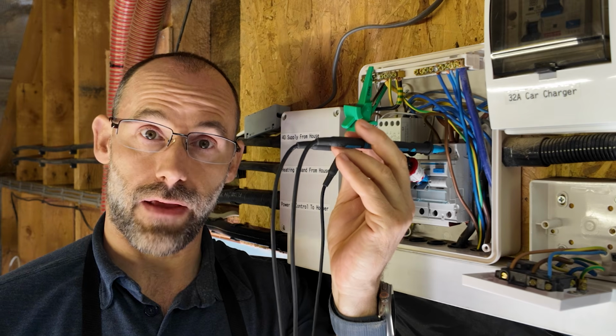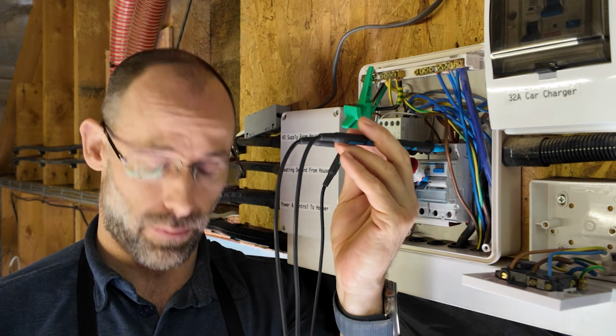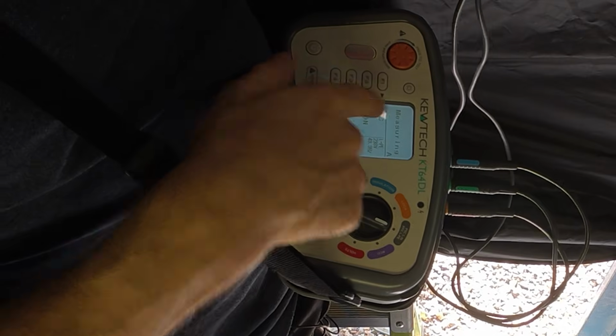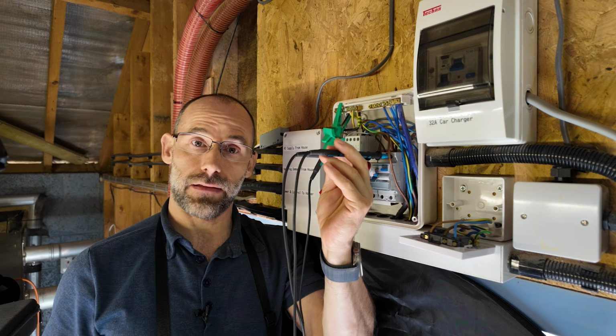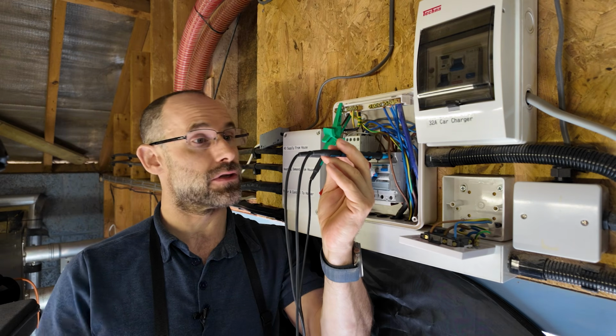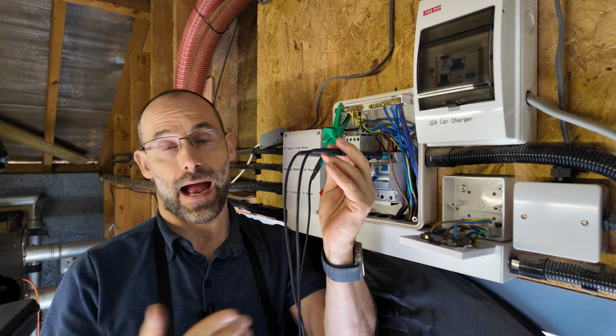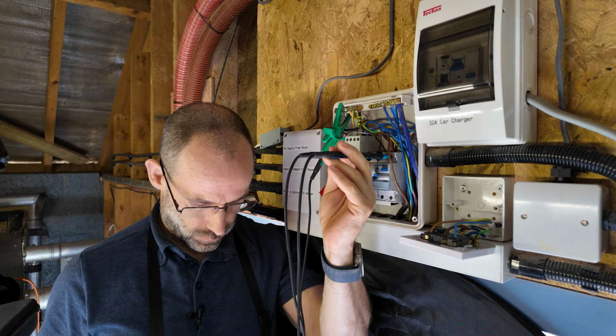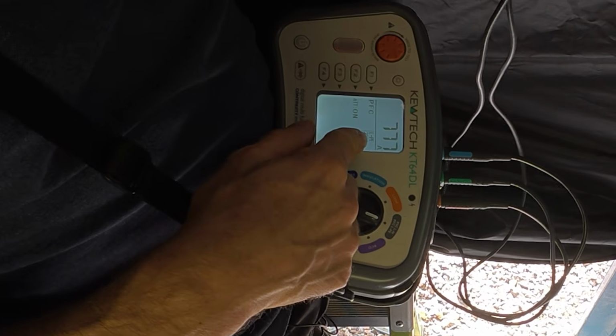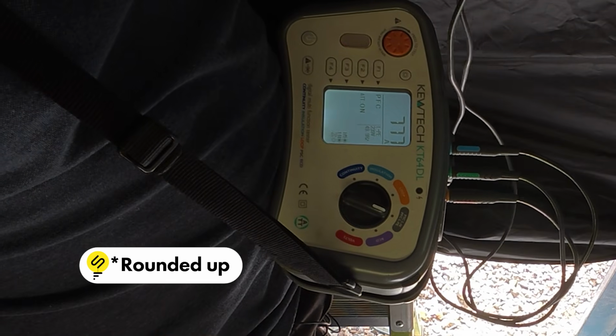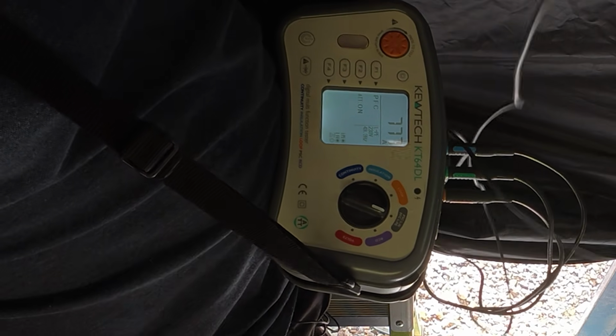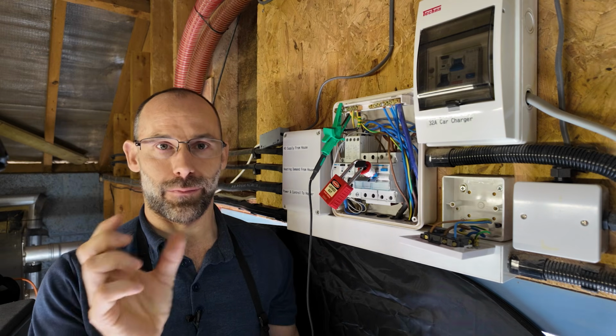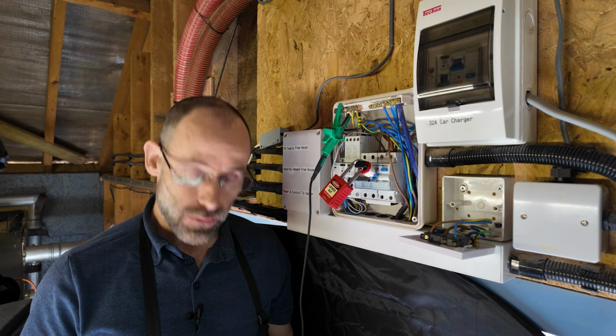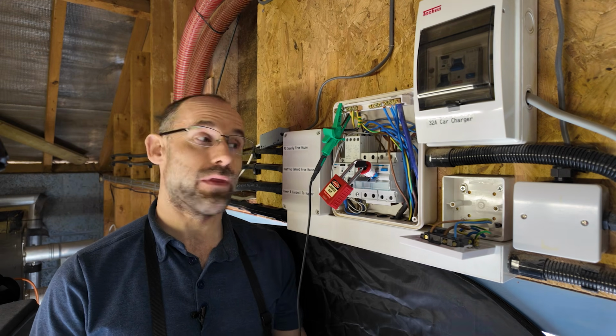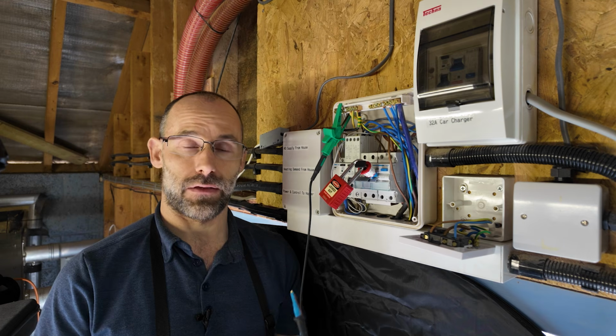For this fault current test, we're going to get the 3 leads set up as before. We're going to ask the meter to tell us a PFC, the prospective fault current. It's going to estimate how much current would flow in a condition where the line and the neutral accidentally became connected together, known as a short circuit. If we look on the meter here, it says 777 amps, or rounded, 0.78 kiloamps, with a number of significant figures reduced. So that's a little less than 1,000 amps, well within the 6,000 that these breakers can handle.